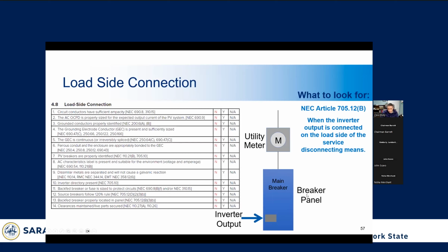So for example, if you have 100 amp service, and you have something that's just sucking power on your panel, and you're using 100 amps of service plus whatever you're providing for your solar, at no point in this panel should there be over 100 amps. You want to prevent that. So that's why you have the power coming in from the utility on one side and the power coming in from the solar on a different side.